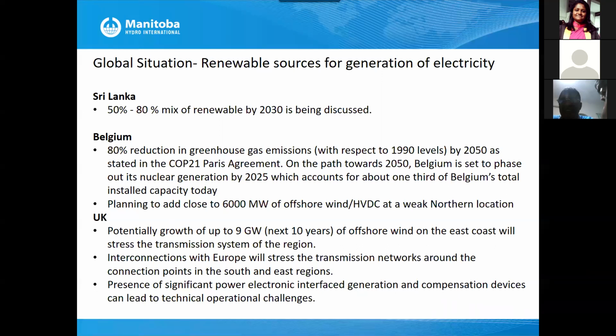So that area of the grid is very weak. In order to achieve this target, adding about 5 or 6 offshore large-scale wind farms and 2 HVDC links, if engineers don't come up with more cost-effective control system design-based solutions, they will have to spend probably $1 billion extra on expensive mitigation equipment.